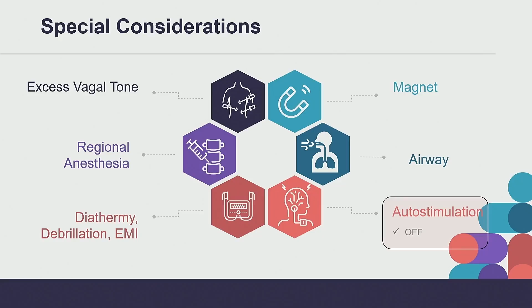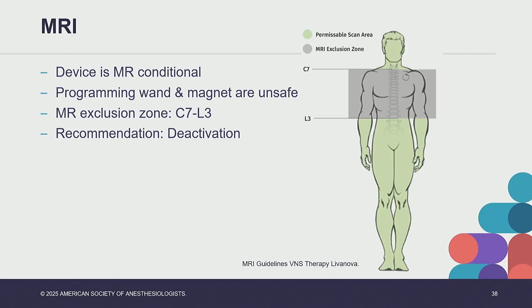And lastly, if a patient does require an MRI, it's important to note that VNS are MR conditional, but the programming wand and magnets are not. Furthermore, it's important to highlight the unsafe MR exclusion zones, which are parts of the body that should never be scanned under any circumstance. This varies from the level of C7 all the way down to L3, depending on the VNS model as well as the MRI. Deactivation of the VNS device is recommended, and interrogation with reactivation after. Additionally, no scanning is recommended within 2 weeks of actual implantation, so as to avoid inadvertent movement of the device.